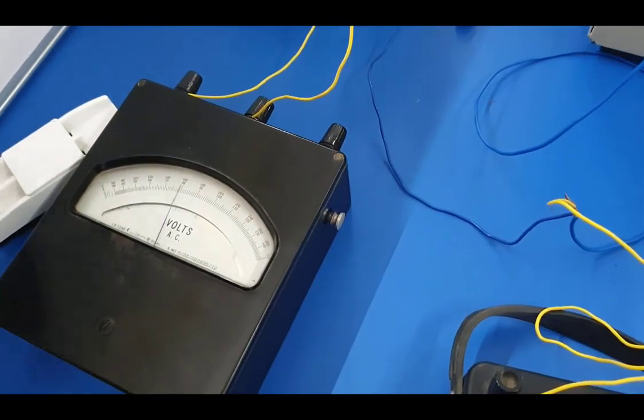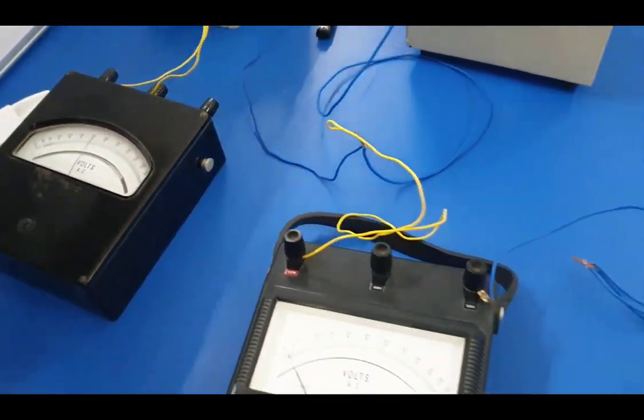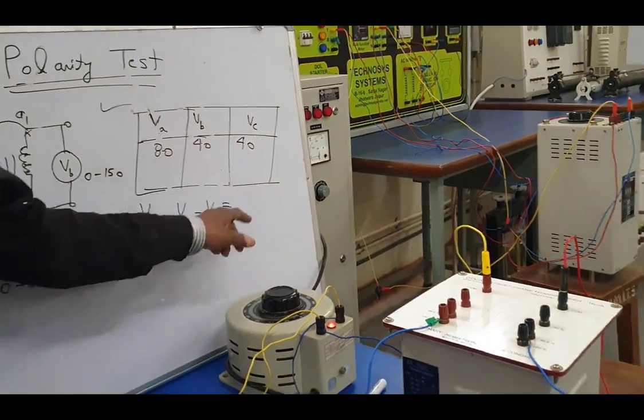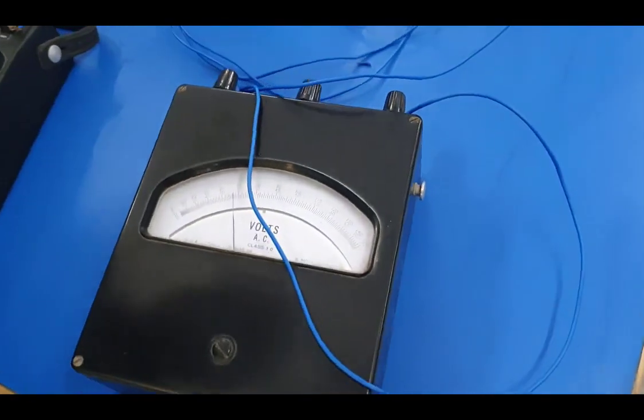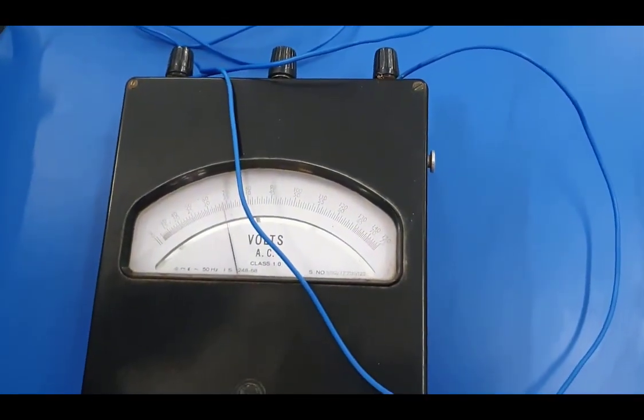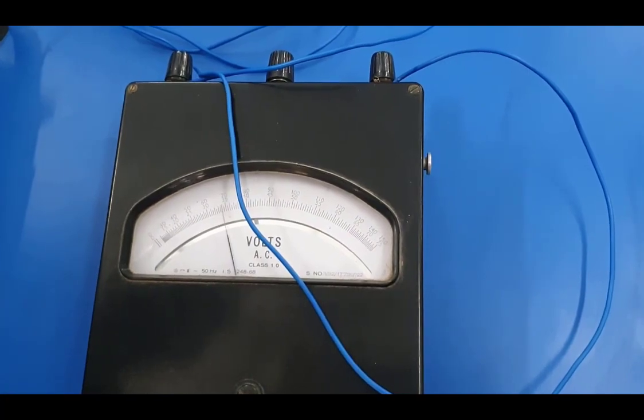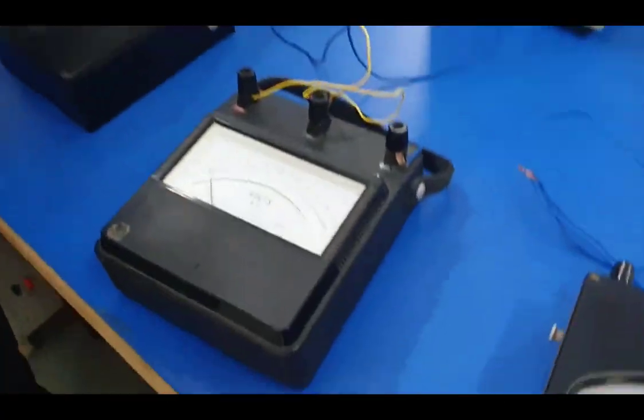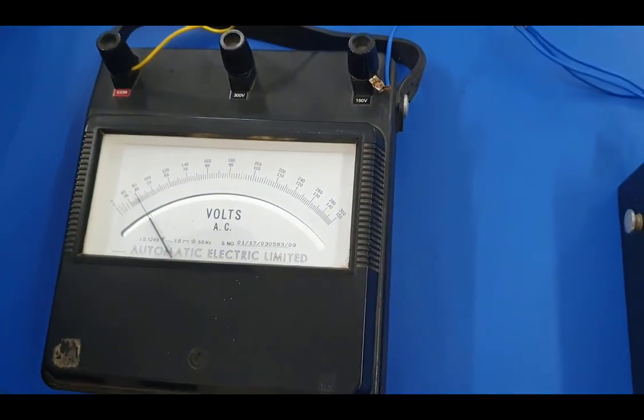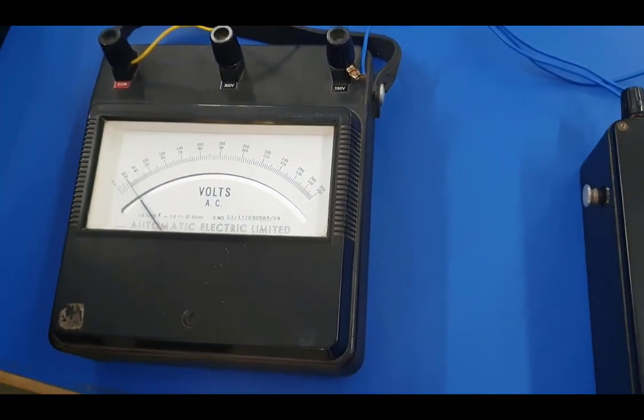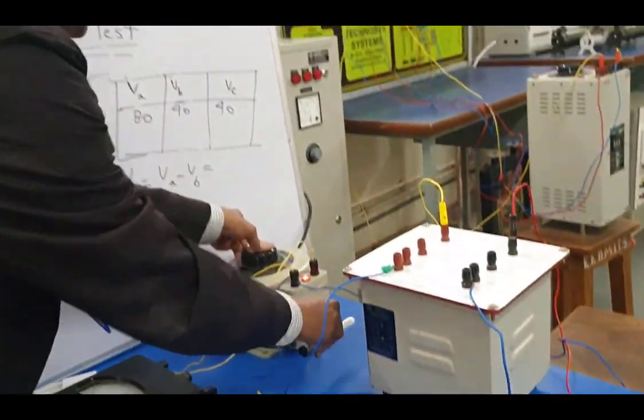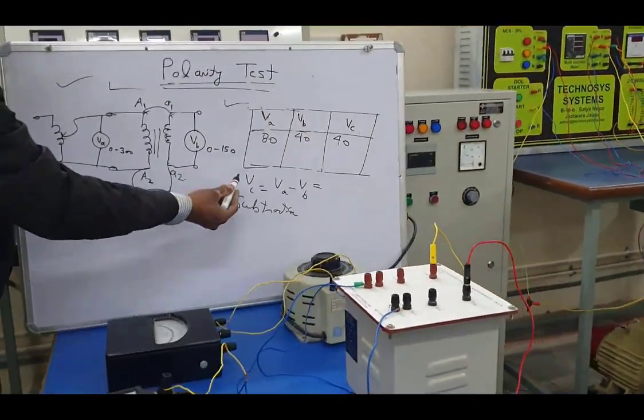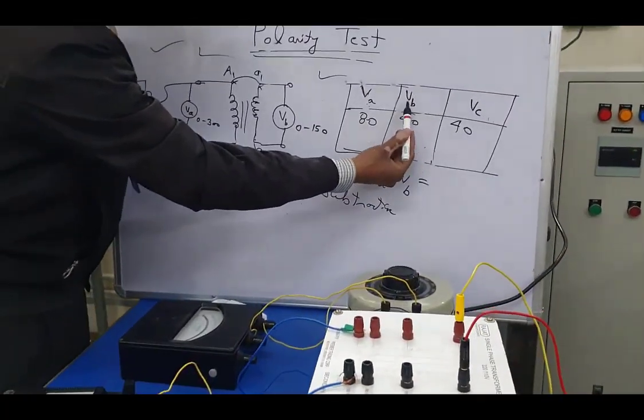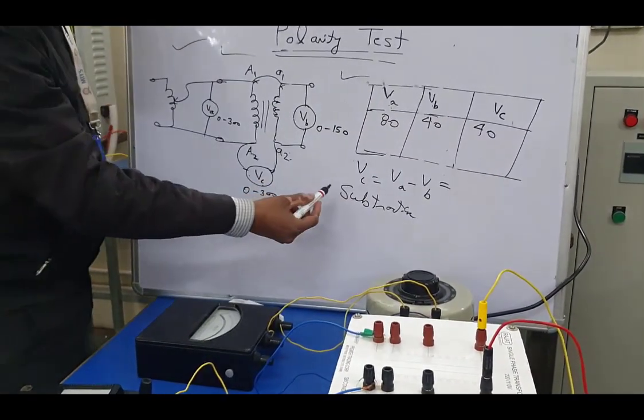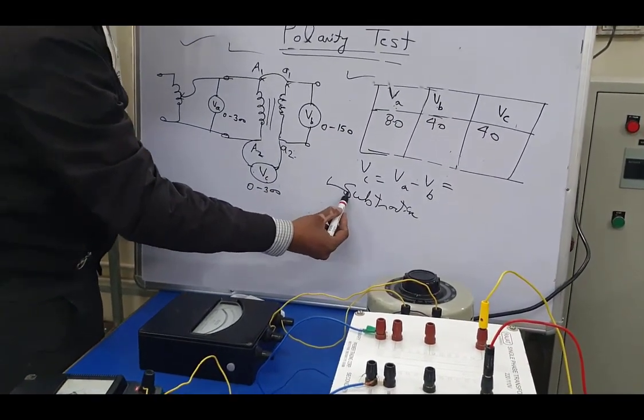So this VA value is 80, and corresponding to this we observe the secondary voltage VB. This is approximately 40. Actually there is an error, it is showing 35, but it is near about 40. And this VC indicates 40. So on these readings we conclude that VC is the difference, VA minus VB. It means in that case we find the polarity is subtractive.